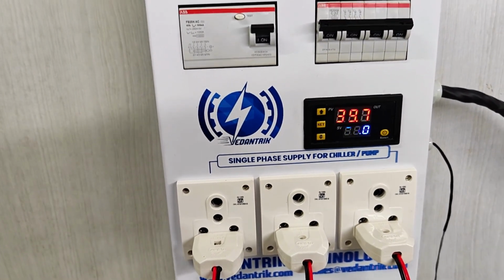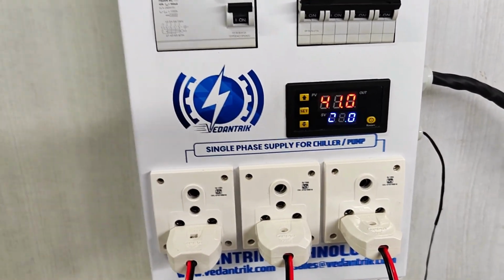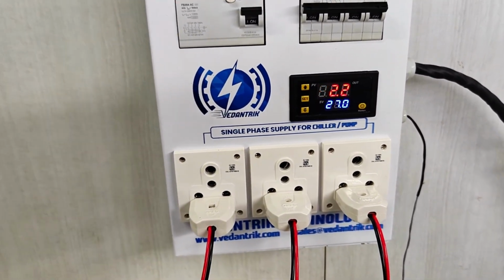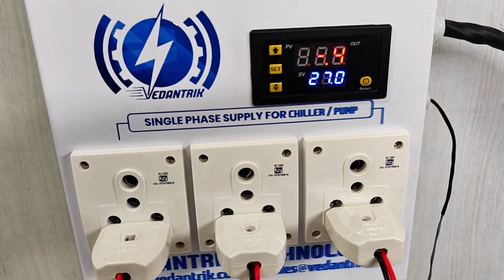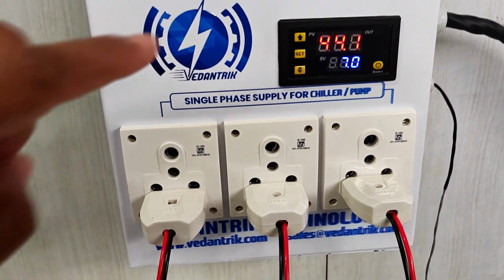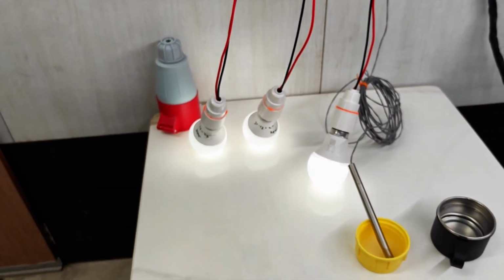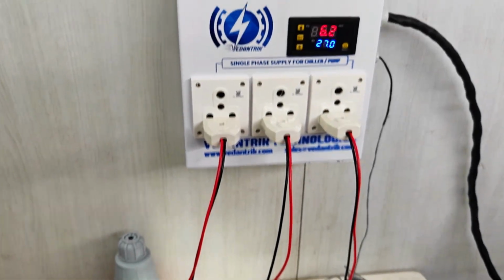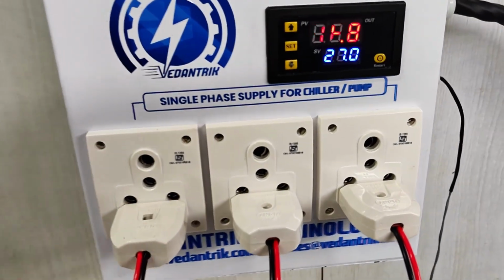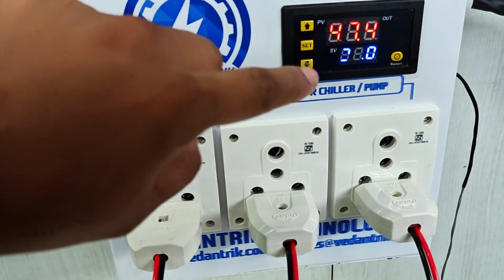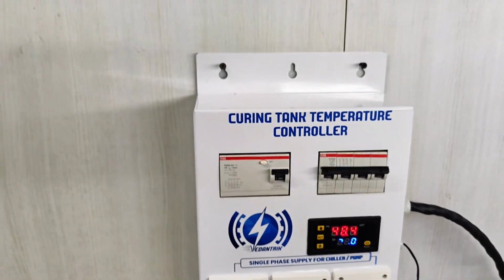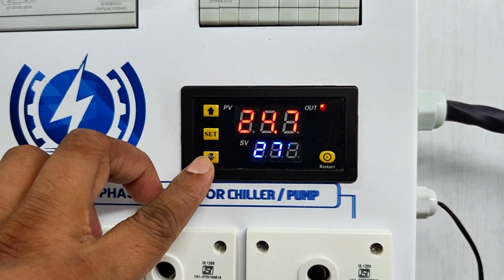Why do we require to go till 29? As per the IS standards, the range is 27 degrees Celsius plus minus 2. So why increase the temperature till 29 degrees Celsius? Let's cut off the heater at 27 only. So even if you want to change these settings, you can change it from here. So here we can see how to change the setting.